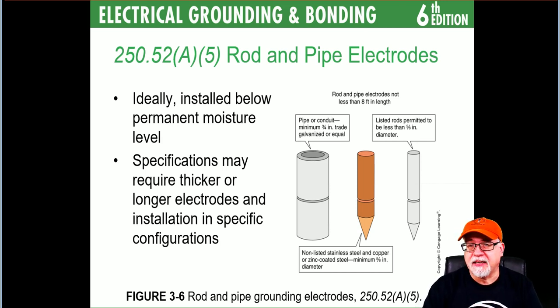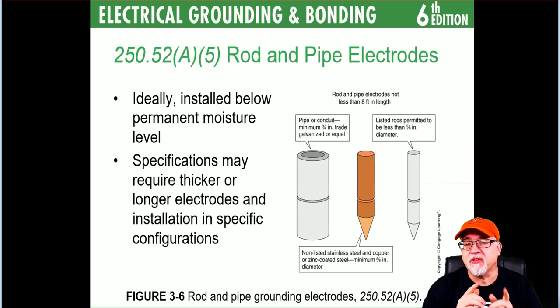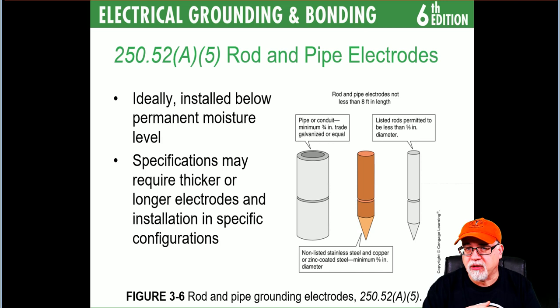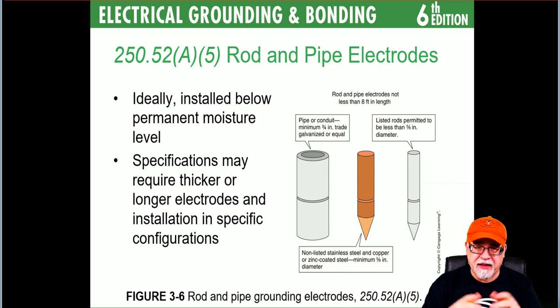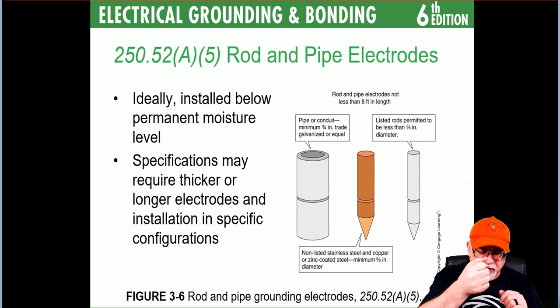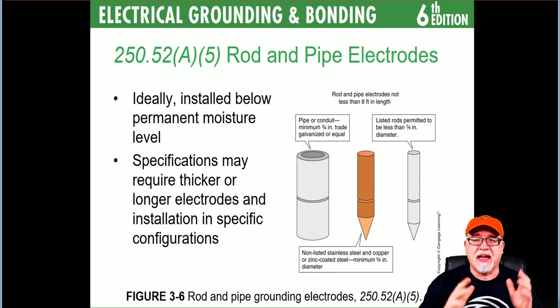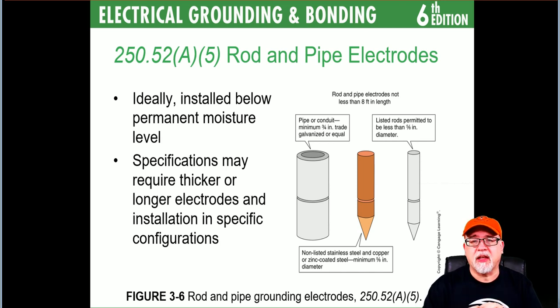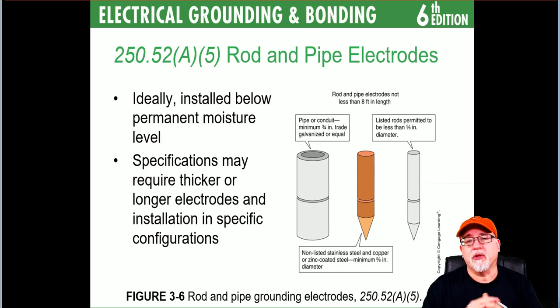Ground rods have to be driven not less than eight feet in the earth. If you hit solid rock, you can switch to a 45-degree angle. If you can't do it at that angle, you're allowed to dig a trench and bury it. You always have to start with an attempt to drive it. Don't place a ground rod in loose backfill and expect it to be acceptable — the code says it has to be driven. As an electrician, I would wait until the backfill is in place and final grade is set, then drive my ground rods.